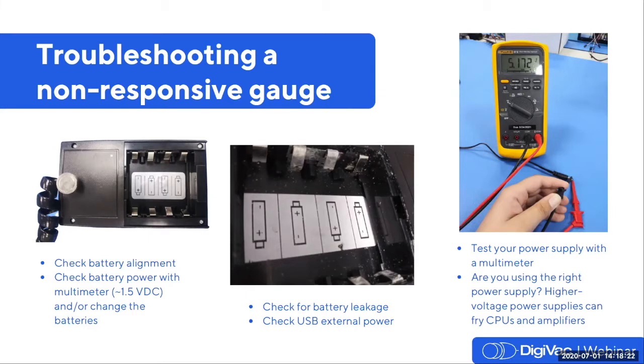However, this cable is not a battery charger. Some customers may mistake it for one, but it's simply external power and will not replenish dead AA batteries that may be left inside the gauge. This type of setup with the USB cord is common in long-term installations such as transformer cleanouts, where the gauge cannot just be turned off to replace its batteries, as it will be logging and recording data and pressure over the course of perhaps several days.